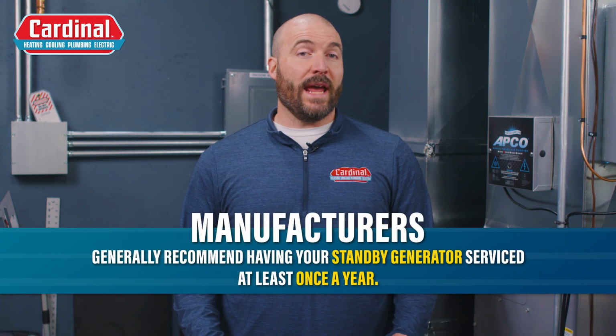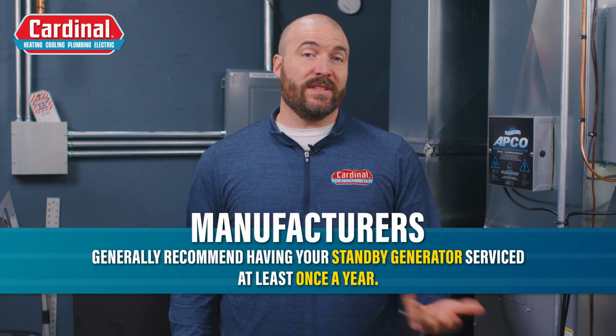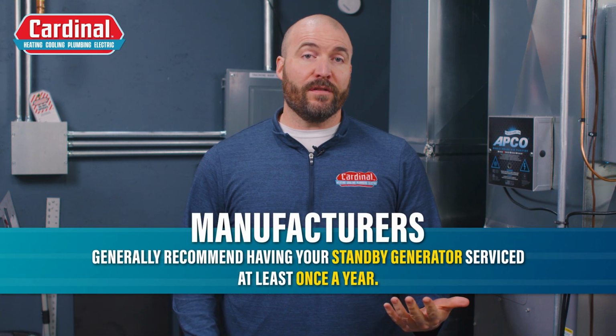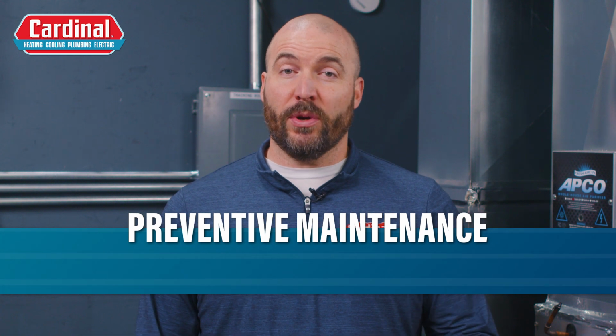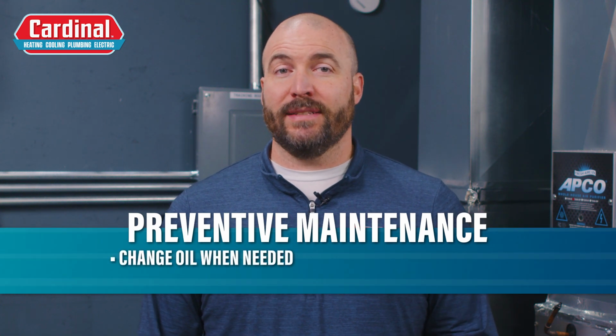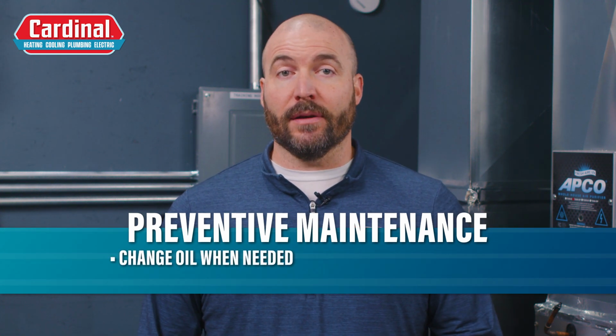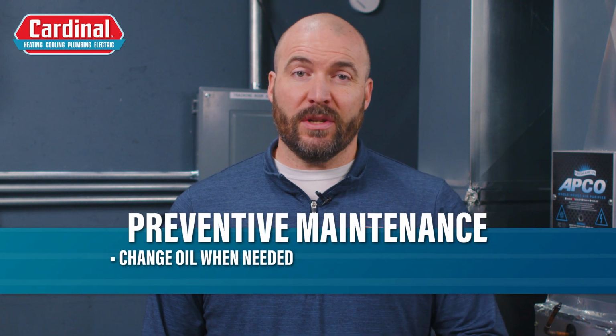When it comes to maintaining a standby generator, it really depends on how often and how long you run it for. Most manufacturers will recommend having it serviced once a year, and most standby generators will have a light or screen notifying you when you need to have it serviced. It's good practice to familiarize yourself with the inner workings of your standby generator. Like a car, your generator will need to have its oil changed after a certain point. This can vary depending on the manufacturer and model. A maintenance schedule is usually included in the owner's manual.